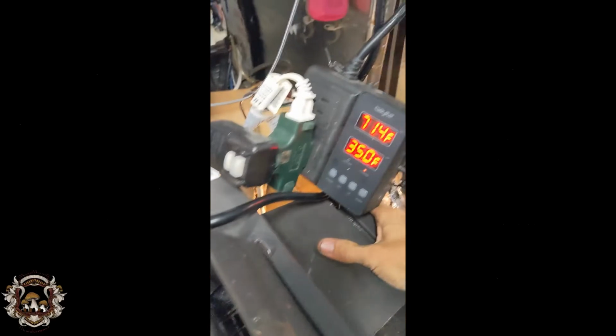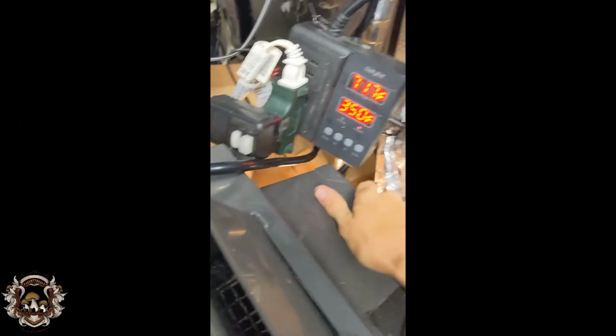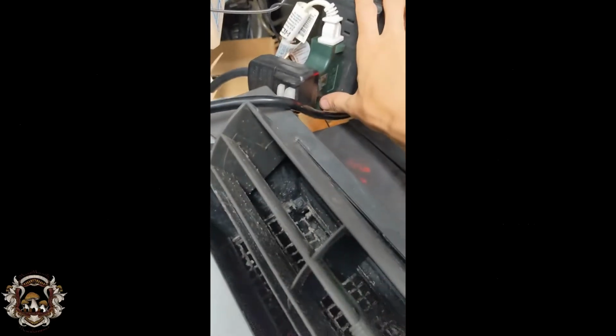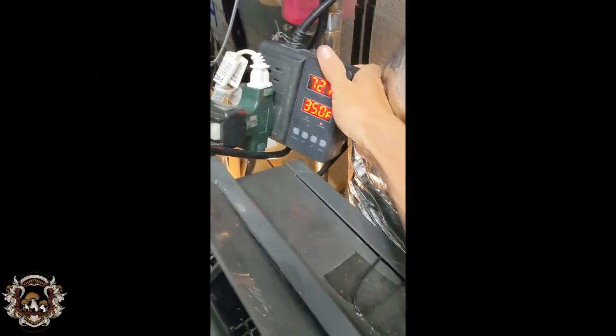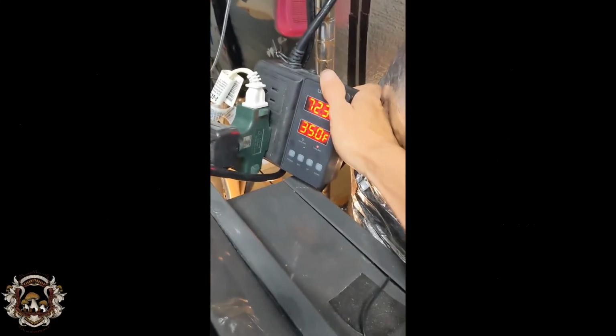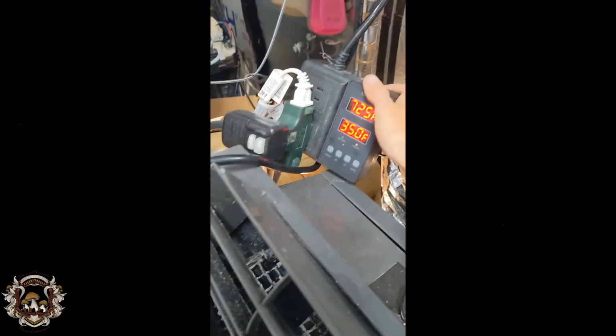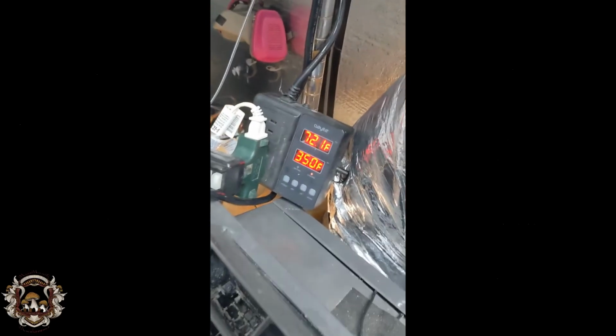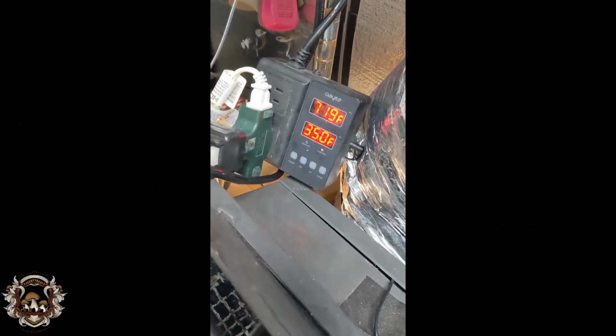Put the sensor here at the bottom of the evaporator, because that's where it gets coldest. If it starts to freeze over, it'll freeze at the bottom first. So when that starts to happen, since this thing runs nearly 24/7 if you let it, it'll turn this off. It's simple as that. This acts as a shutoff if it starts to freeze over, and it gives power to the air conditioner and the light bulb as long as it's not frozen.